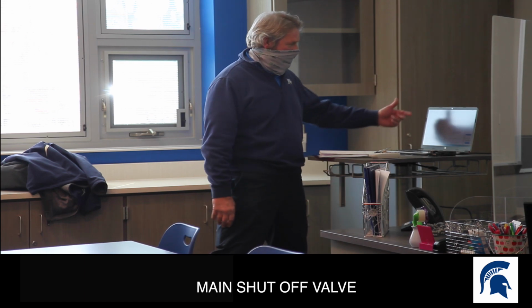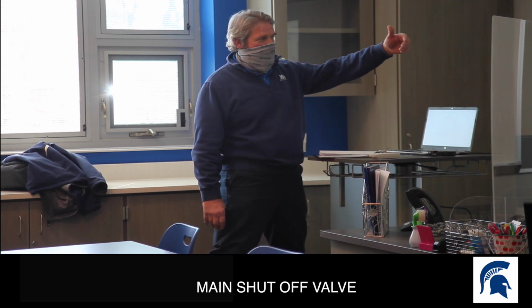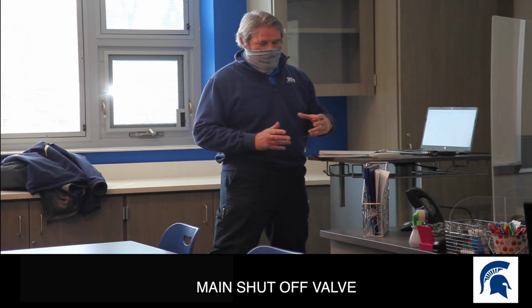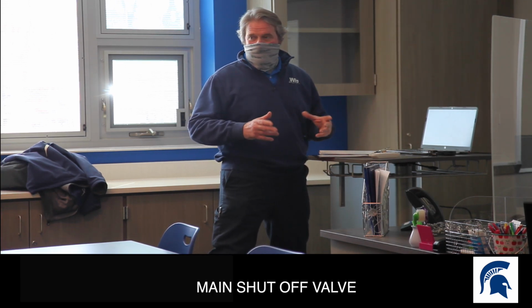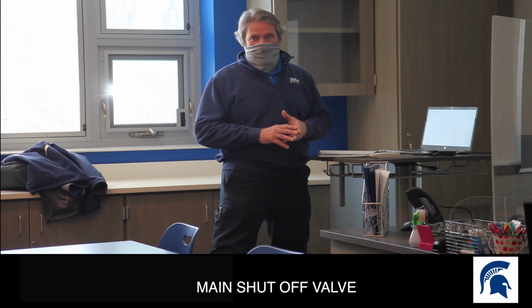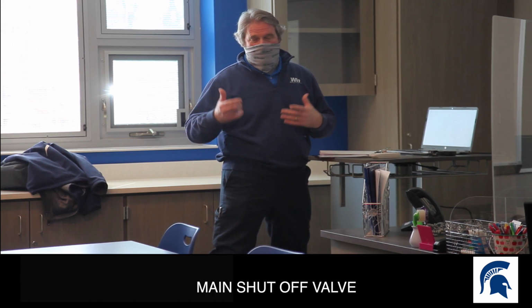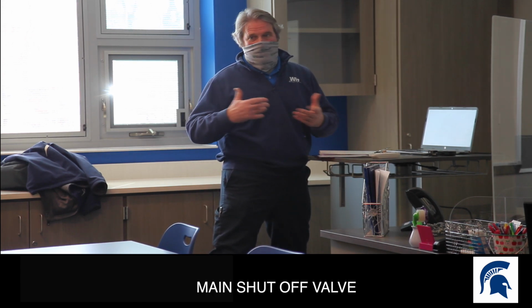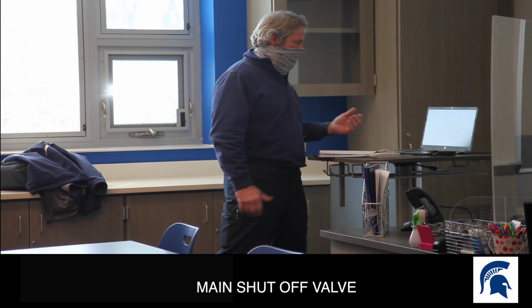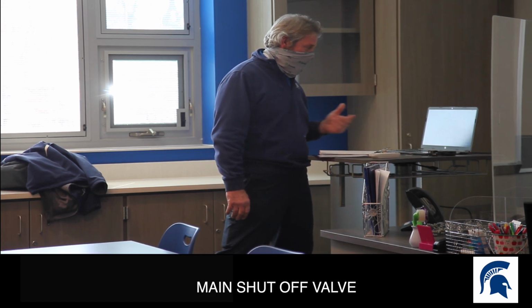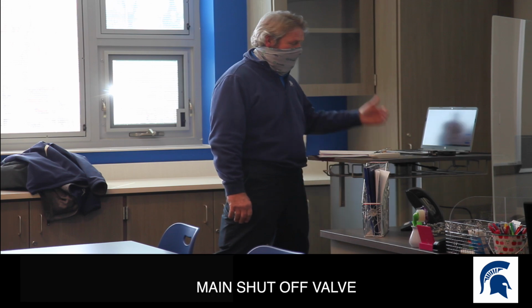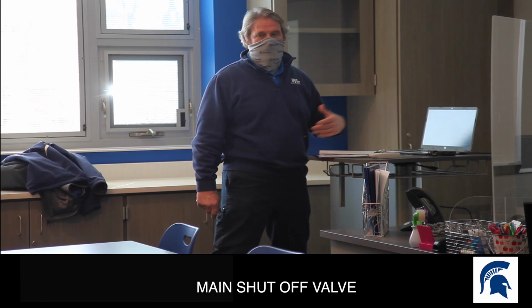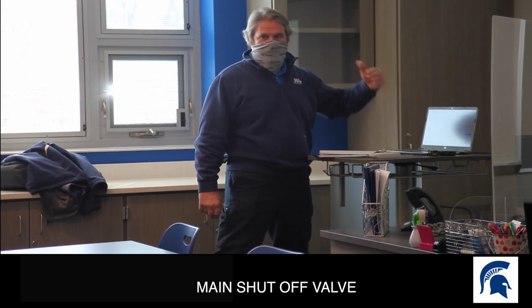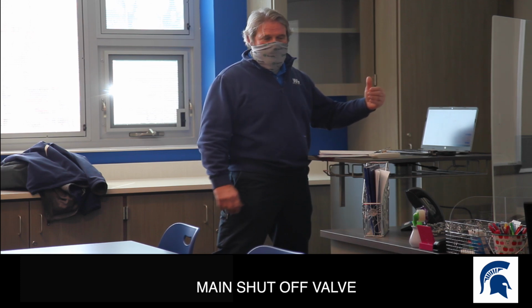And basically, when we go down there we can look at it on the unit itself; the diagnostics are all on that screen. It's got a little computer in there, and it's going to tell you if something fails. It's going to show you what failed. Will it come with a code number on it? Oh yeah, well it tells you, blocked inlet, check this, not firing. Then you go through the sequence.